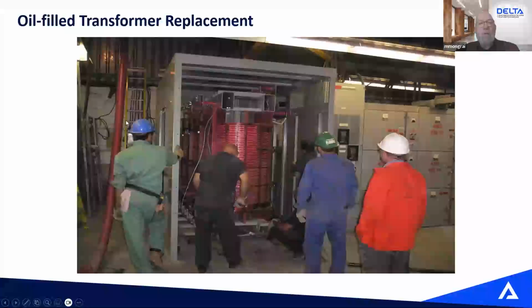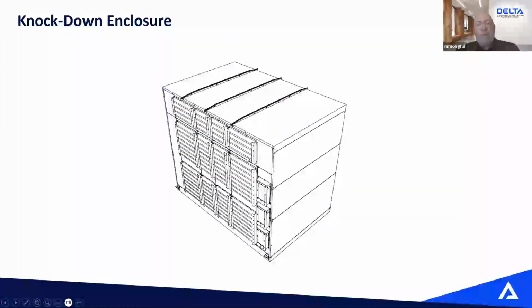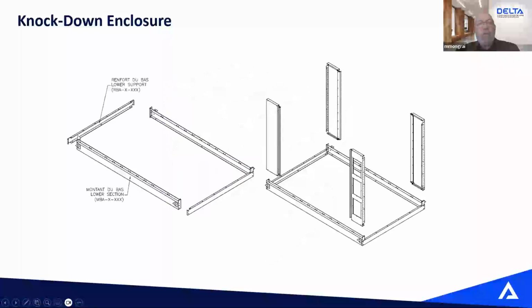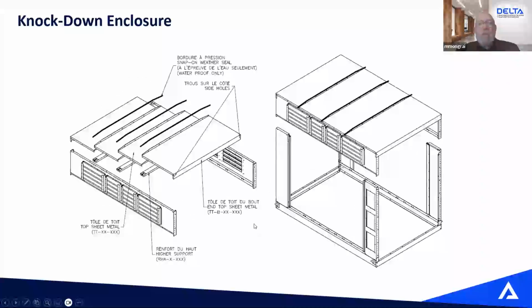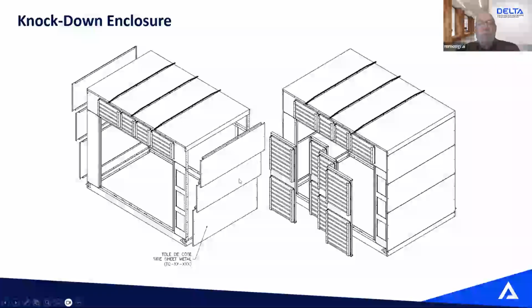So that's your total result, the fully assembled enclosure, but we start with a base. So four sides, and then we have what we call our corner posts. The corner posts go on the base. Then you have your roof assembly. It's made of, depending on the width of the transformer, two, three, four panels with stiffeners, and then the front and the back, and then you drop that on top of your four corner posts. And from there, you put your side panels and you put in your removable panels or hinged doors front and back, and you're back in business. Your enclosure is fully assembled.